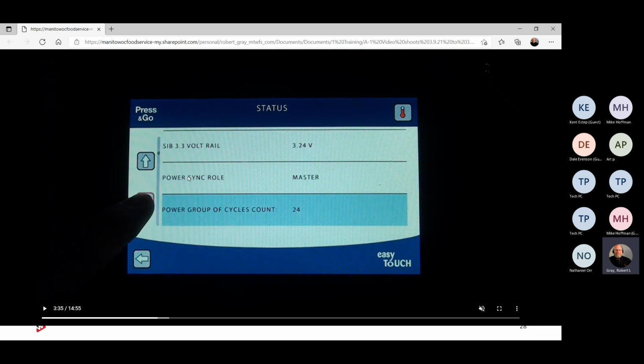Okay, power sync role. All right, this is very important when you have two lanes hooked to the same power cord. You have a master and you have a slave. Essentially, all that does is sync the two units, so you have a properly balanced load on the electricity. That's all it's doing, and it's based off of one being the master and the other one just following suit. I'll show you that in the diagrams when I get to it.